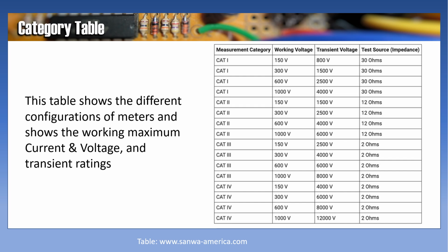This is a table that shows the different configurations of meters and shows the working maximum current and voltage and transient ratings. Notice that the highest working voltage for any of the categories is 1000 volts. And the transient, that is a momentary spike, is only rated at 12,000 volts. If you expect anything more than that, you don't have the right meter.